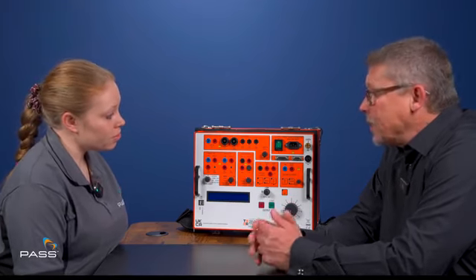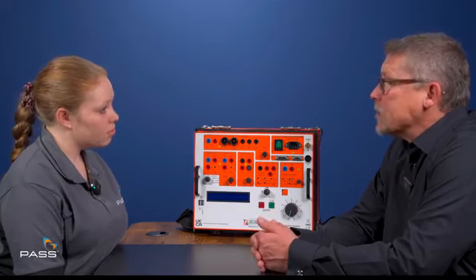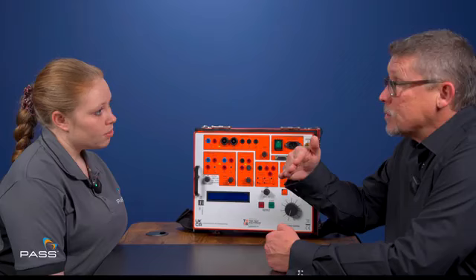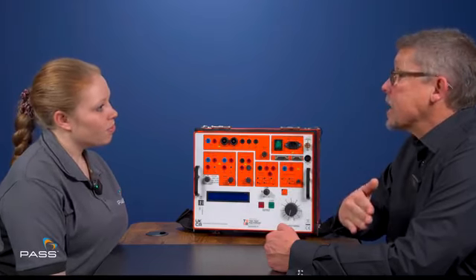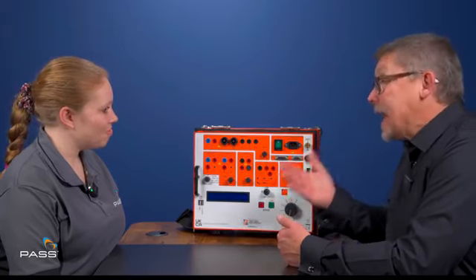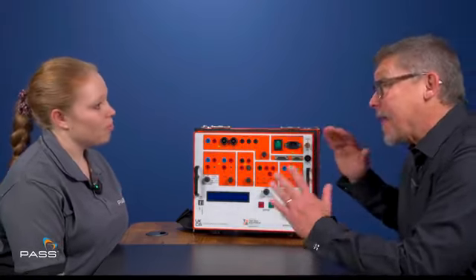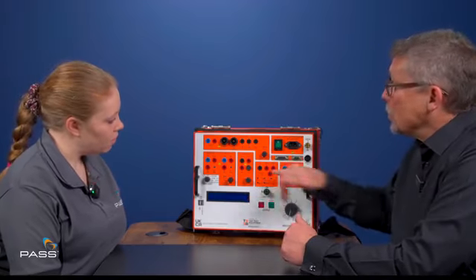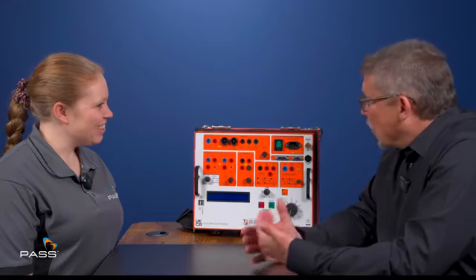It has indeed. One of the things we do with our test sets is when we issue a data sheet, you'll find on the data sheets, we list out the type of relays that these units can test and the type of tests we can do. And what you'll find is if you compare this with its little brother, the 100 ADM, for example, that is a secondary injection set. It's got an output there, and that's pretty much about it. Whereas this, with the auxiliary channel here, frees it up to become a lot more than that. As I said, is it a secondary injection set? Yes. Is it a primary? Yes. Can it test digital relays? Yes. Have we got a lot of control over it? Yes. So what I would say is this is really a multi-tool when it comes to secondary current injection test sets.